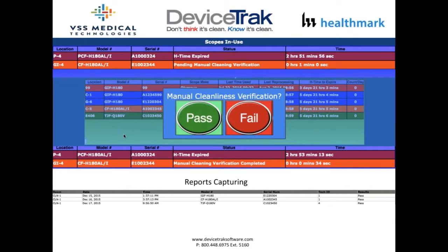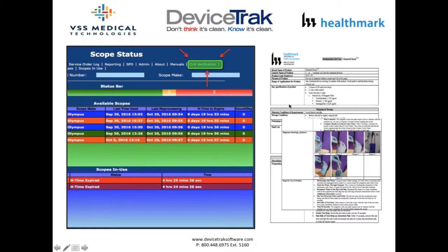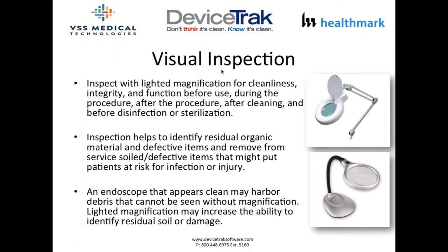DeviceTrak's cleaning verification module captures whether each scope passed or failed. If a scope fails verification, the system prompts return to manual cleaning and the scope cannot advance in the process. All users have the cleaning verification tab available and can reference the products used. Results are captured via reporting.